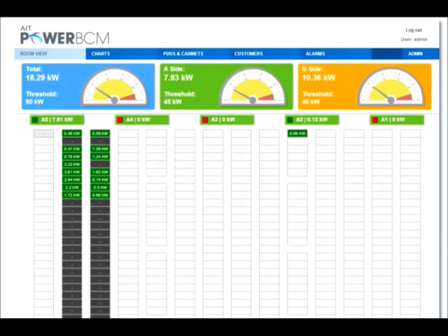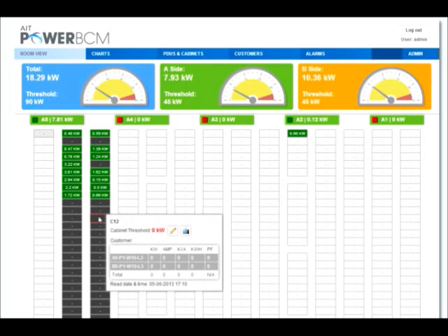The homepage which you're looking at the moment provides a view of the cabinets that are available. You can designate cabinets as not being used where they have no power monitoring required. There are also cabinet designations where the power is supplied but they're not actually being monitored at the moment because they wouldn't have any equipment in. They're ready to be provisioned, along with cabinets shown in green, where there are customers using those cabinets and there are power draws for those cabinets, so there's equipment in them and there's a power draw against them, and the green status would indicate that the cabinet is within acceptable thresholds.